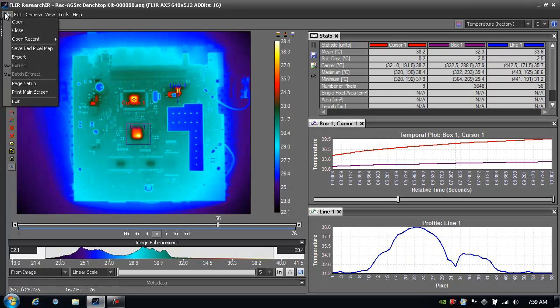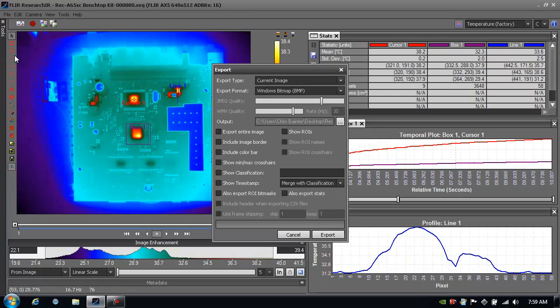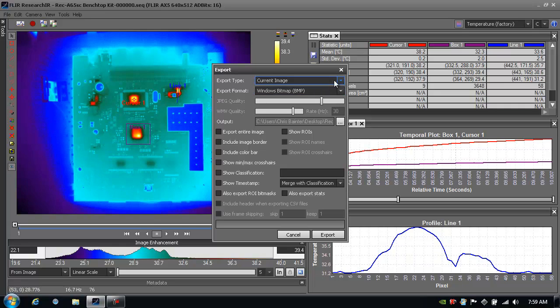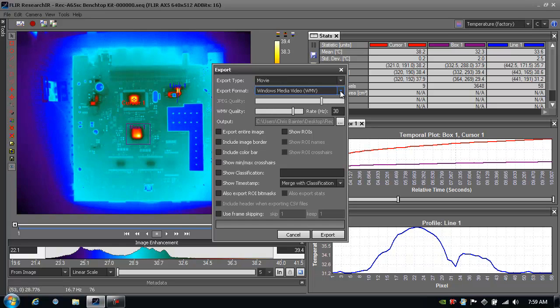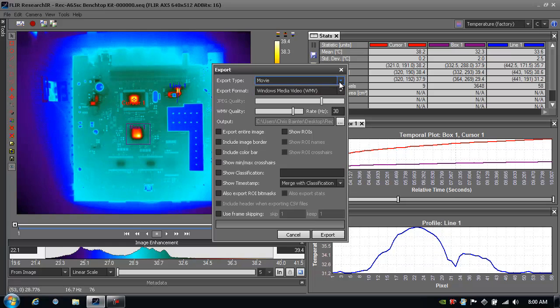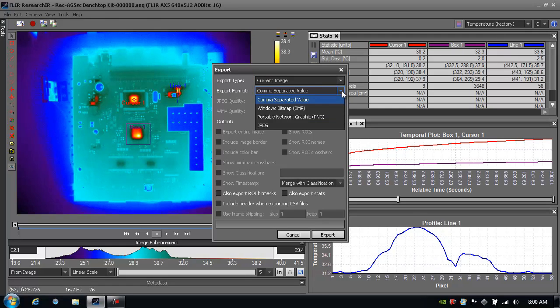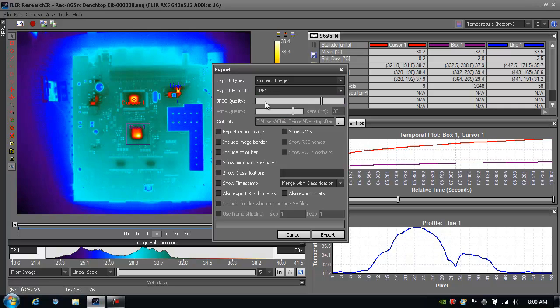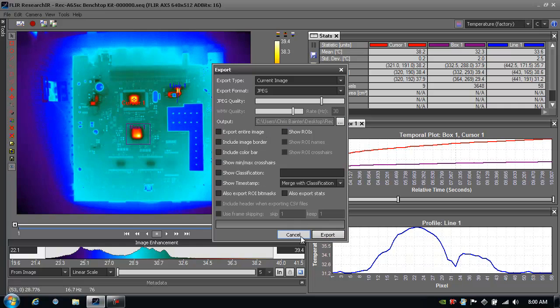But I'll go back and go up to file export and look at some of the ability to export the entire image. So if I choose the current image or maybe I want to export the entire movie. Let's take a look at the movie. I can export it as a Windows media video file. So now I have a really nice color infrared movie that I can share with people. And they don't have to have the software to be able to see what's going on there. A really nice intuitive way to share that data. Or I can choose current image. And of course there's the comma separated value file we've been talking a lot about. But there's also bitmap, PNG, and JPEGs. If I choose a JPEG I can even choose the compression quality and some other items here. But the key thing is I just want to choose where I want to record it. Save that file off to and a few other options and I just hit export.